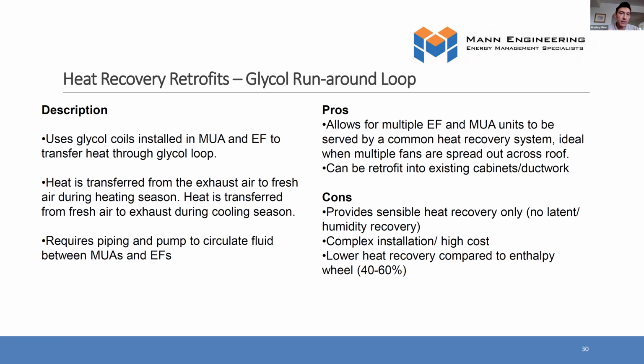So this would allow the exhaust air to transfer heat into this runaround coil, and that heat would be transferred into the fresh air coming in through the makeup air. So it's just a way of moving heat around across multiple units. The main downside is the efficiency is not going to be as good. It's pretty low grade heat, so you're looking at less than 50% heat recovery typically, and the cost of actually running piping around the roof could be potentially high. So those are some of the main downsides there.